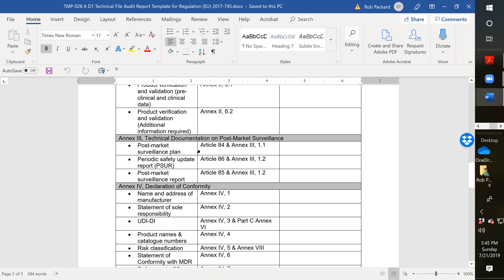Then we get into Annex 3. This is where we see the biggest change from the MDD. You are always required to provide a post-market surveillance plan, but a lot of companies didn't understand what that was. And they've clarified that in the MDR. It's not just your procedure. What they're looking for is a plan that's specific to each product or product family. So you need to have a plan as well as your procedure.